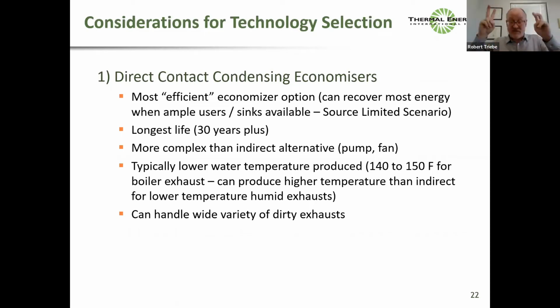Okay, and so I'll go on about this option. The other thing is, it's the most efficient economizer when you have more users than heat source. We're going to talk about this more. Source and sink limited. When you're developing projects in heat recovery, you either have more waste heat available than you have user, or you have more user available than waste heat. If you've got more source than sink, we call it sink limited, because the user is going to dictate your project size. If I can recover 10 MMBTU, but I can only use 5, I'm going to build for 5. But if I can use 20, but I can only recover 10, I'm going to build for 10.